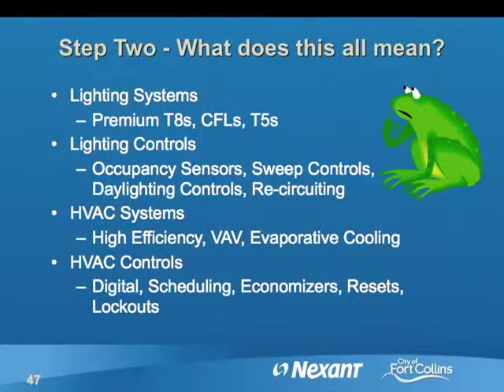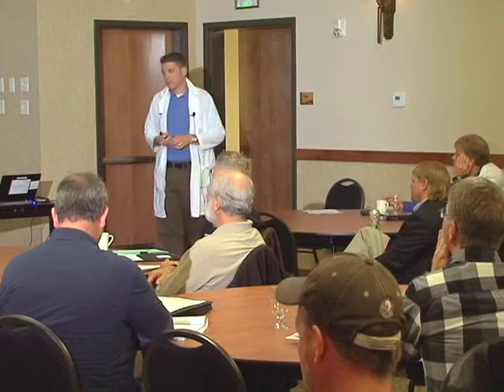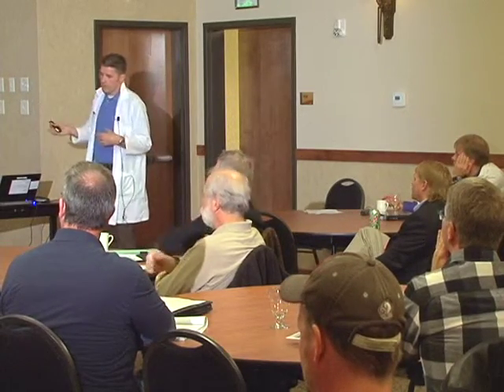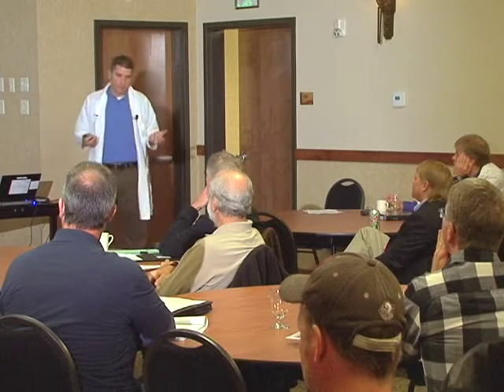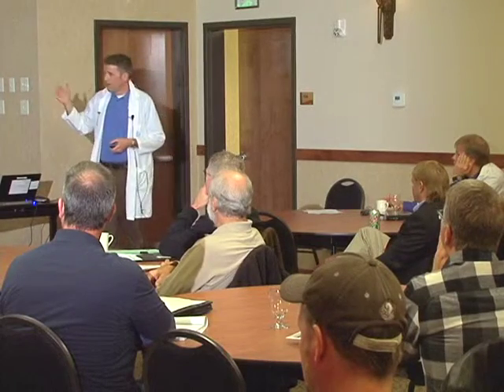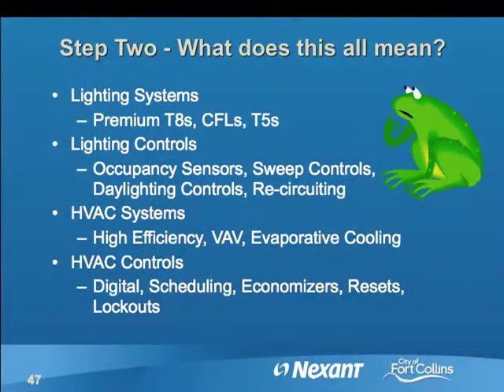As far as HVAC systems, are they 5 years old or are they 50 years old? If they're 50 years old, it's probably time to look into replacing them. If you replace them, you're looking at high efficiency systems. Again, things get more efficient as time goes on. VAV is good. Evaporative cooling is great. To give you a comparison, the SEER rating of a DX air conditioning unit might be somewhere around 12 to 15. Evaporative cooling is about 40 to 50, so we're looking at three times more efficient. They're very efficient, and that's what we recommend using if you can install them.